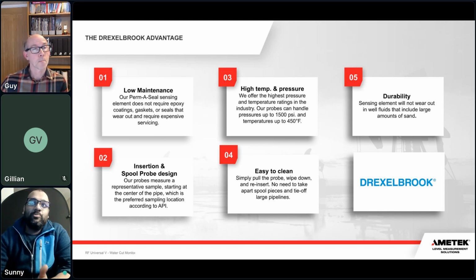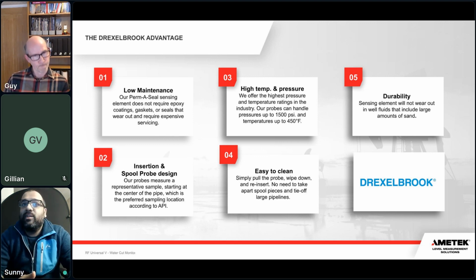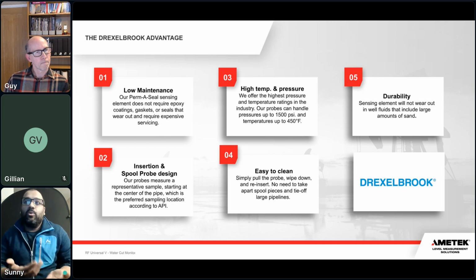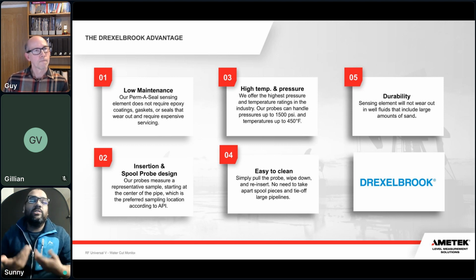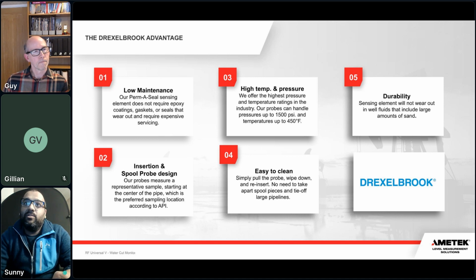So again, the Drexelbrook advantage is low maintenance. Our probes, in an ideal installation, if it's installed correctly and calibrated correctly, you just set and forget. You shouldn't have to pull them. You shouldn't have to clean them off. Compared to our competitors, we do offer some of the highest pressure ratings, up to 1500 psi and 450 F. Durability, because of the coat shield and the injection molded design, we've never seen any of these probes break off in the field. They're not just pressed in and layered. They are injection molded, making them very rigid.